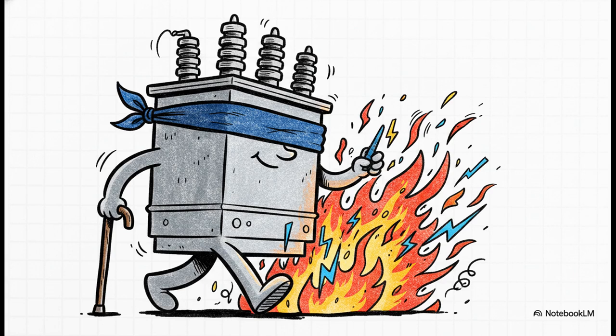Disabling those filters severely undermines the security of the entire system. Real, catastrophic faults can and totally do happen at the exact same moment a transformer is being energized or overexcited. If you desensitize the relay, the transformer is flying completely blind to a real fire-starting fault happening during that startup. You must always investigate the root cause of the nuisance trip instead of just compromising the relay's logic.